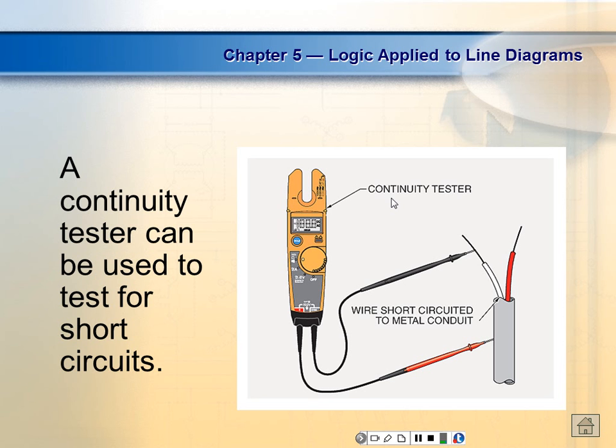Yeah, that's about it. And by the way, check that. If you measure 0 volts, you need to get in the habit of doing that too. For one thing, you've got different leads down here. You put it on ohms, and you want to check ohms. Most of your handheld meters have 3 sockets in them. You have a common, you have a volt, and you have amps. These clamp-on amp meters only have 2, because what they're trying to do is make the meter common. And what's nice about the meters that have 3 leads is when you go from volts and ohms to amps, you literally have to pull out a lead and move it over somewhere.